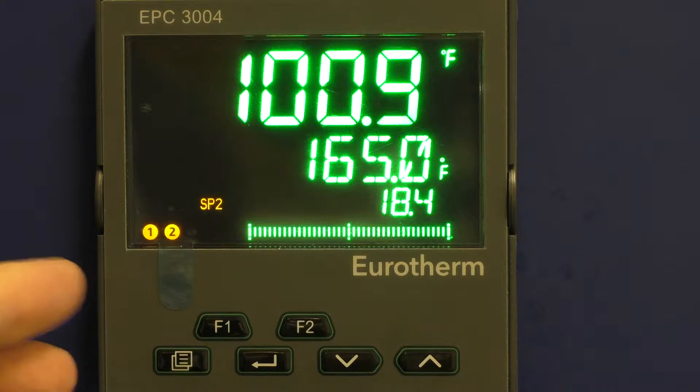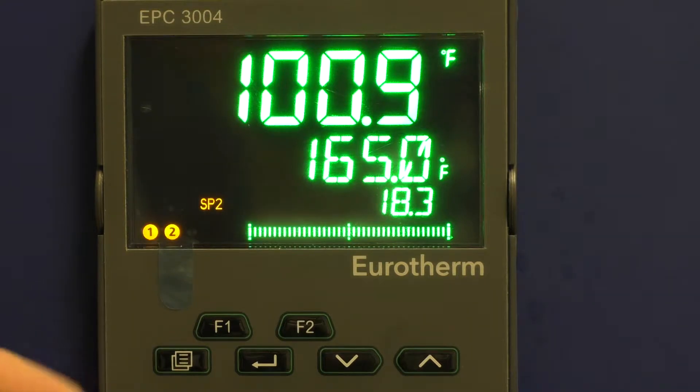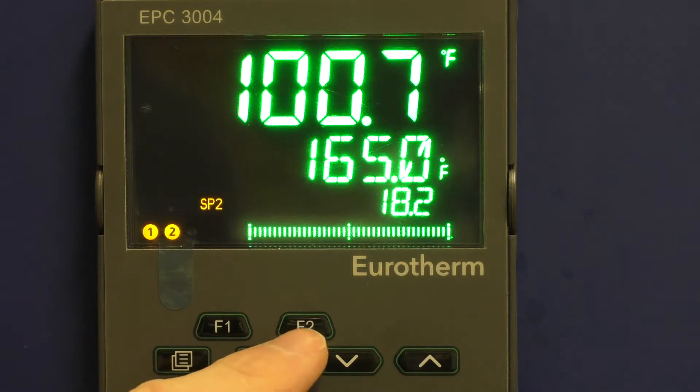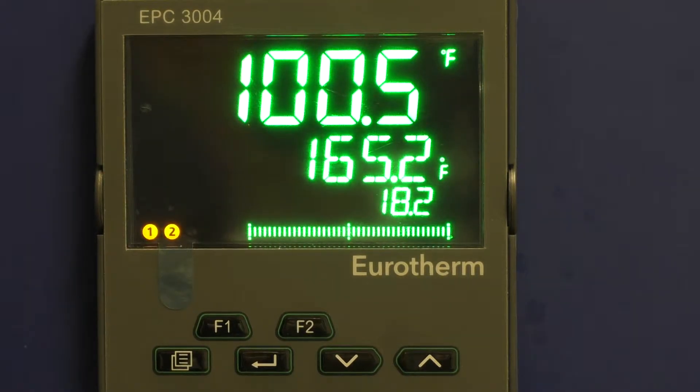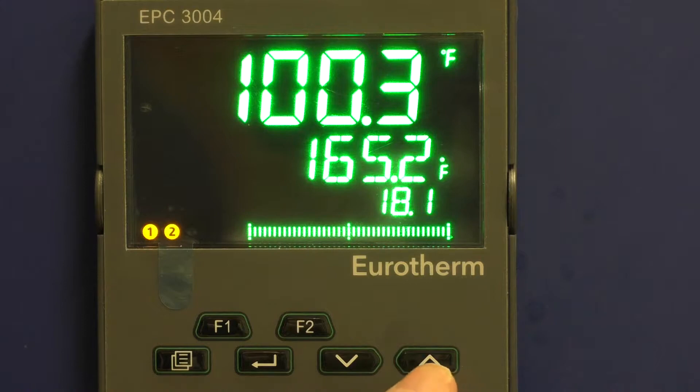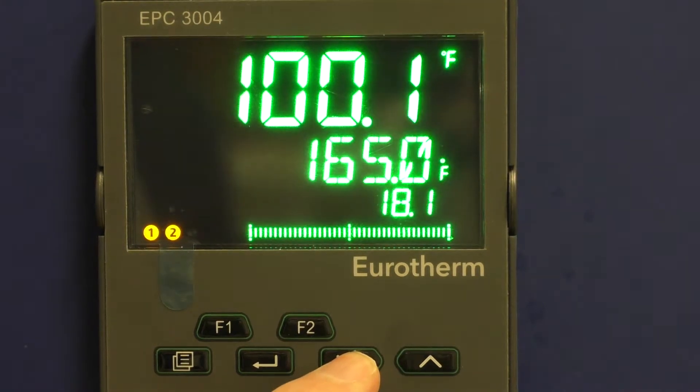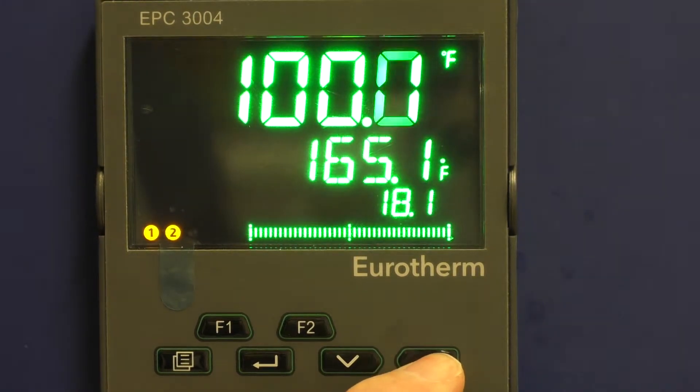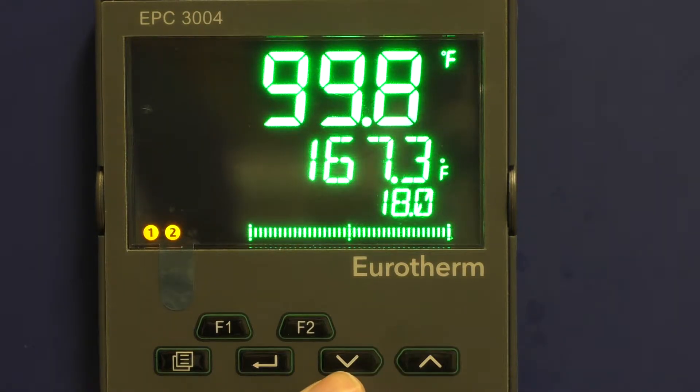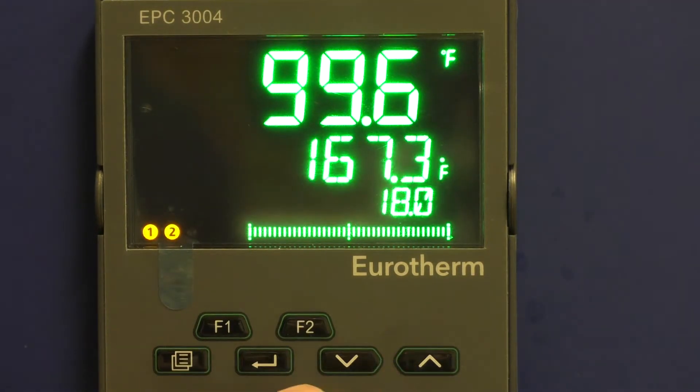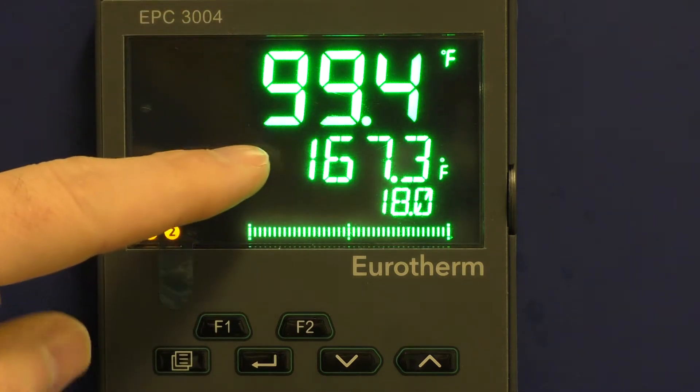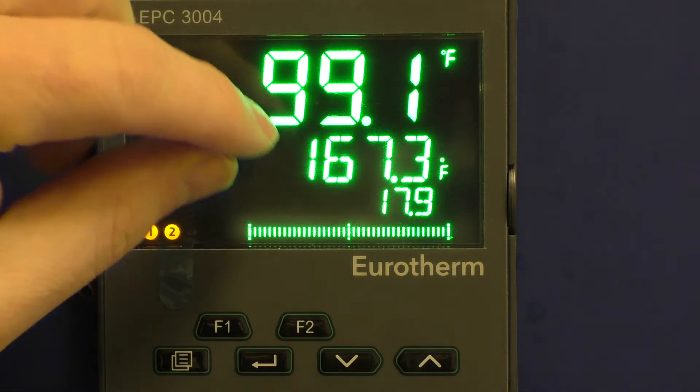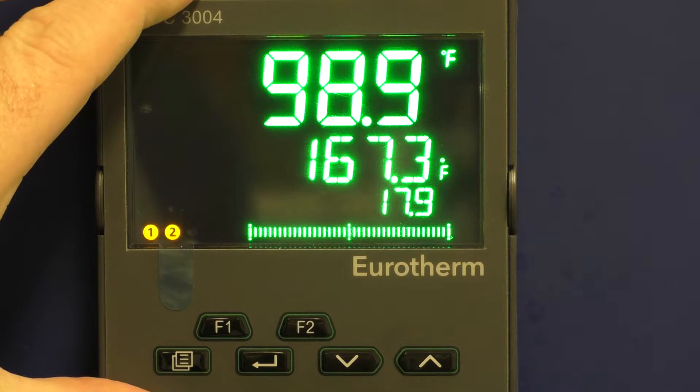If you want to run the dryer in manual mode, i.e. no timer, you simply hit F2 one time. To change the temperature, you can use these up or down keys. Once you make a change, you stop and wait for what you changed to flash. That means the controller has accepted that input.